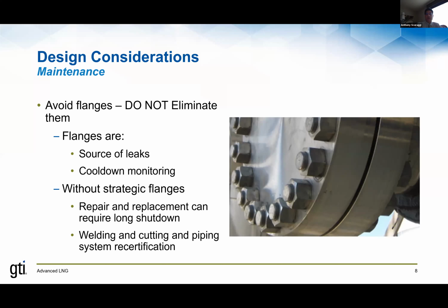All that welding work on piping systems requires you to then recertify the piping through pressure tests or some other means. When you initially do the removal work and you do the cutting of the pipe, you have to make sure that you properly purge the systems to remove any combustible mixtures. So it becomes a very, very, very time-consuming job to do maintenance work. So you have to balance that, assess that against the likelihood of leaks in your piping systems if you're using flanges, and determine which flanges should strategically be in place and not be eliminated.